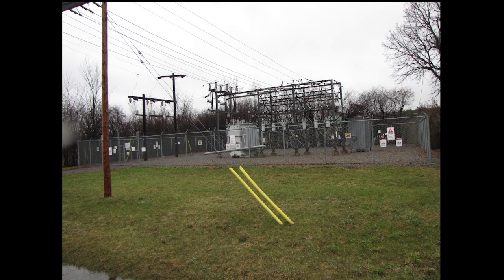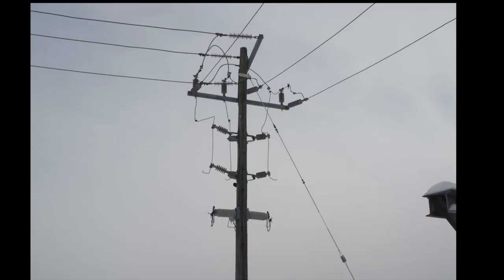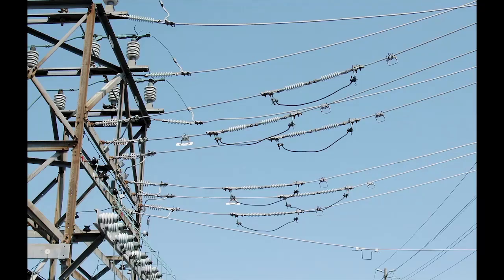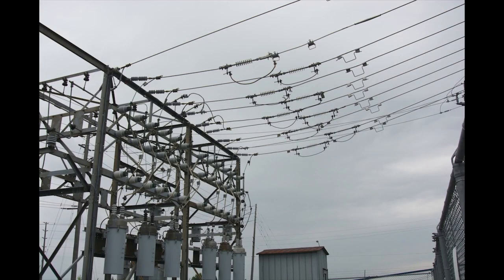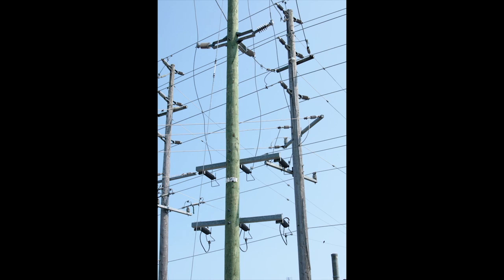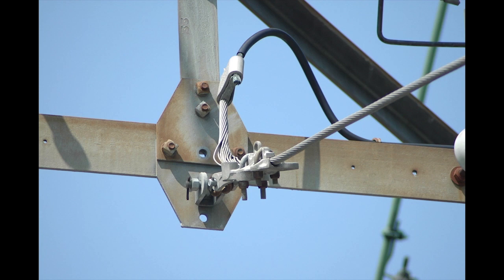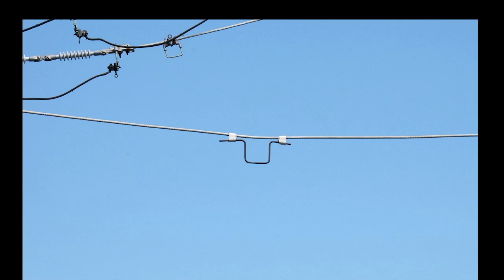A lattice structure station, also known as an Item 27 or Jones-style station, typically has the station ingress overhead on air-insulated strain bus from the MUS pole. The station egress is typically an air-insulated strain bus that is supported by an H-frame. The egress is then tapped to the lines outside the station. The MUS directly connects to the station ingress at the MUS pole and the station egress, bypassing the transformer, low-voltage bus, and reclosers. The neutral bushing on the MUS is also connected to the distribution system neutral at the overhead egress exiting the station.